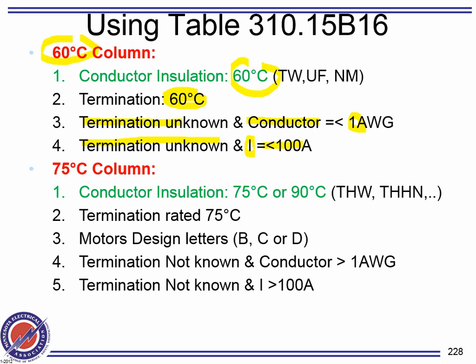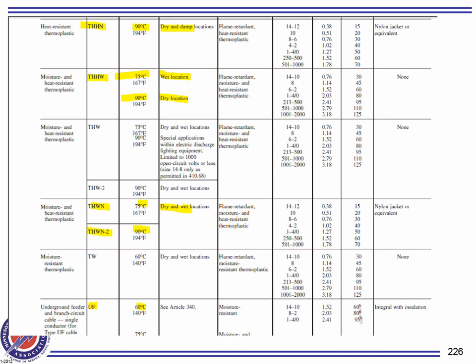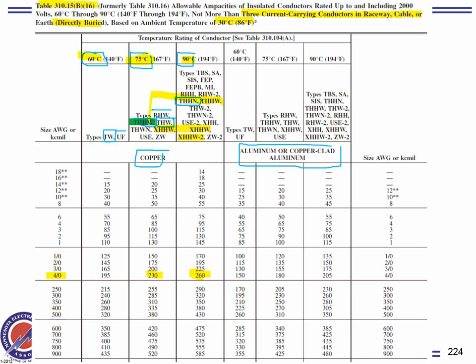If you know what the terminations are, the conductor says... column. Okay, so you go back to the 60-degree column here, and you start with number 1 right here. If you're number 1, you're stuck basically. If your conductor is number 1, you are in the 60-degree column right here, unless you know what the lugs are and the conductors are rated for more than 60.